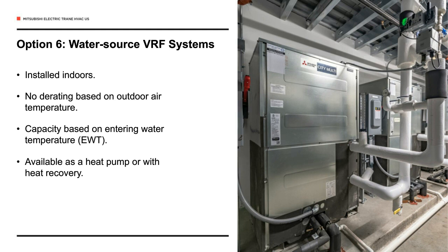You also get better performance and better efficiency because you have a water loop which you're rejecting heat into or pulling heat out of depending on the mode of the condensing unit. But that water loop is a much more defined temperature range, generally between about 60 degrees Fahrenheit and 90 degrees Fahrenheit. So it's real similar to a traditional water source heat pump system. If the water loop gets below 60, you turn on a boiler and you heat the loop up. If the water loop gets above 85 or 90, you turn your fluid cooler on, pull the loop temperature back down. So the VRF condensing unit's not seeing temperatures that range from 10 below zero to 95 degrees Fahrenheit. It's seeing a much more controlled temperature. Plus, it's easier to pull heat out of and reject heat into water as compared to air. So that's why you see some efficiency increases.